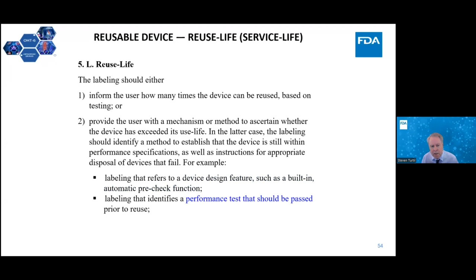And lastly, labeling that recommends visual inspection along with acceptance criteria or failure criteria. Unacceptable deterioration includes corrosion, discoloration, pitting, and cracked seals. I heard somebody in the user community say that they have a mantra that pitting is the beginning of the end of the use life of a product. So as soon as they see pitting, they know to dispose of the device.